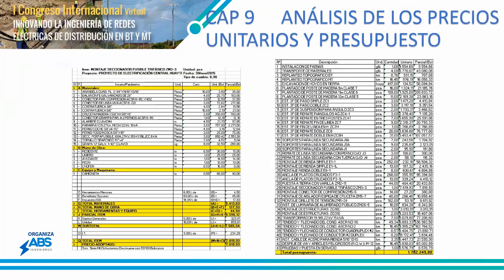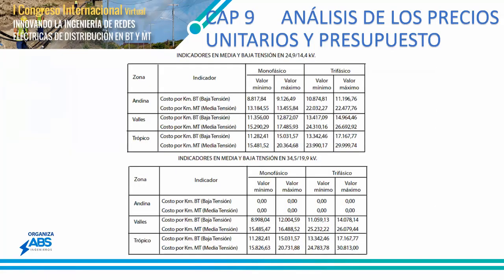Estas son tablas de Excel que manejamos para generar análisis de precios unitarios y un presupuesto general. Por ejemplo, aquí tenemos una estructura — es un seccionador — que tiene su cantidad de materiales, mano de obra, equipo, gastos de materiales, utilidad y gastos generales, y de ahí nos genera un precio unitario. Por la cantidad del ruteo de nuestro proyecto de electrificación rural, podemos llegar a un monto total del proyecto. También es muy importante manejar estos precios referenciales.